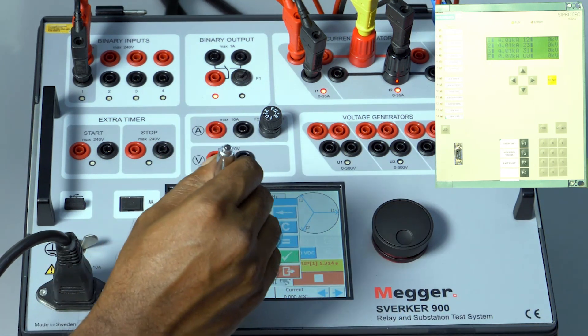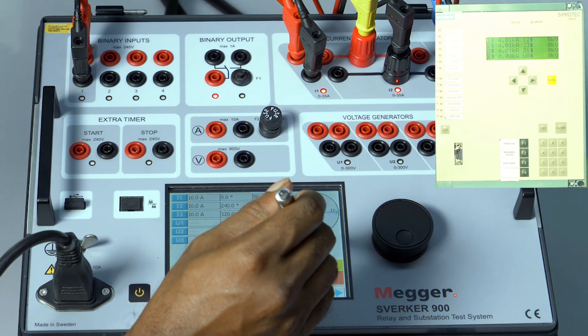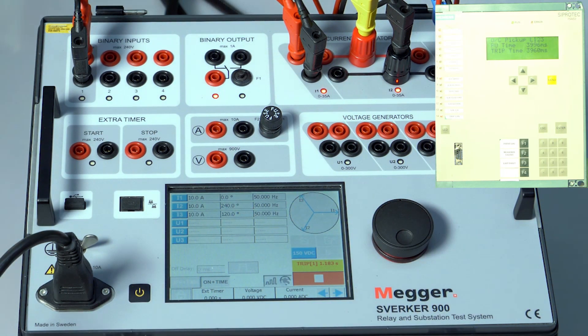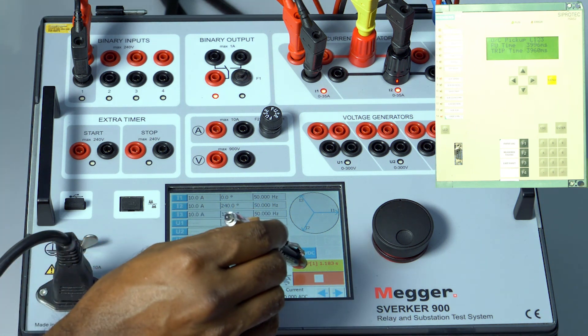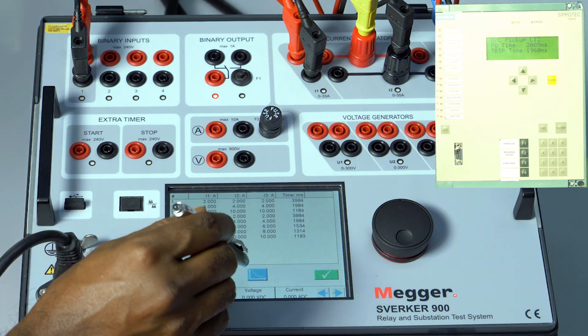Ten amps. So you can test as many points as you want, and after completion press the stop button. We get a table here. You can see the actual tripping time and the corresponding current. By clicking on this graph, you can get the IDMT characteristics.